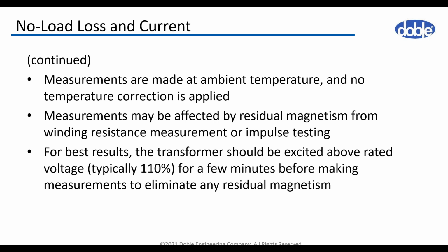During the no load test, the transformer shall be approximately at ambient temperature, and no temperature correction is applied to the result. The result may be affected by remnant magnetism, which is caused by some of the measurements. One of these is winding resistance, and also another test is impulse testing. The impulse test also affects the no load loss, which is usually higher after such tests. Usual practice is to over-excite the unit for a short period, let's say 5-10 minutes, to eliminate this residual magnetism before we actually perform this no load loss measurement.